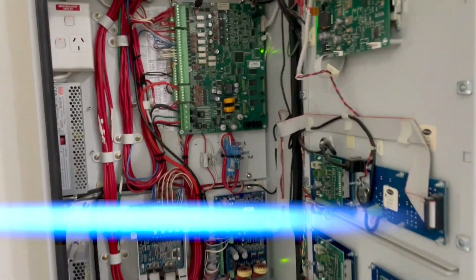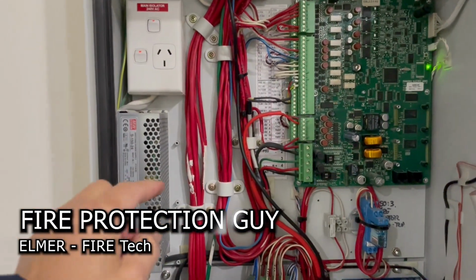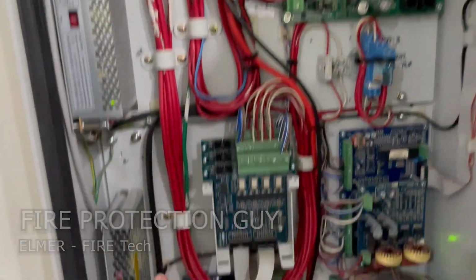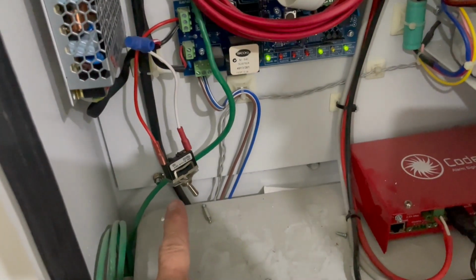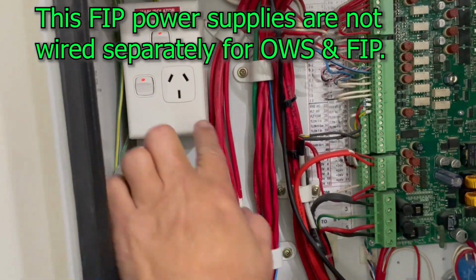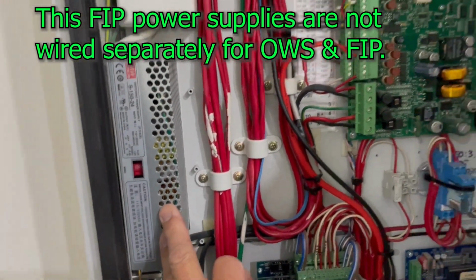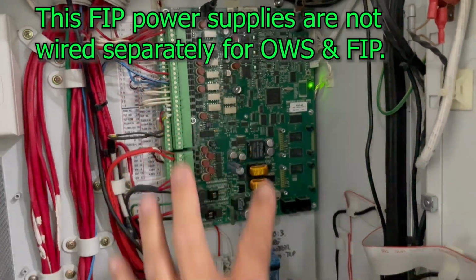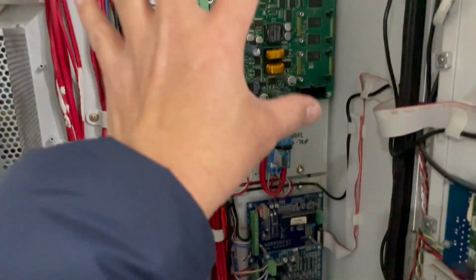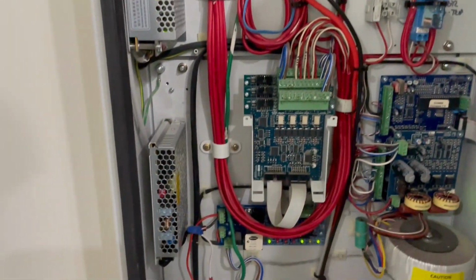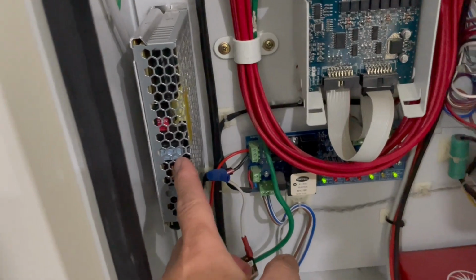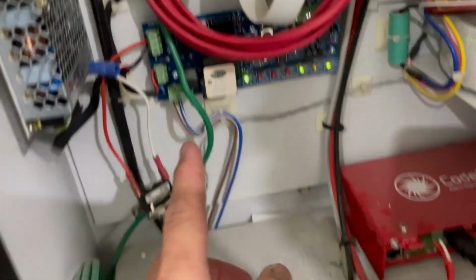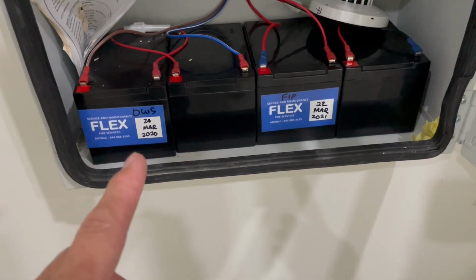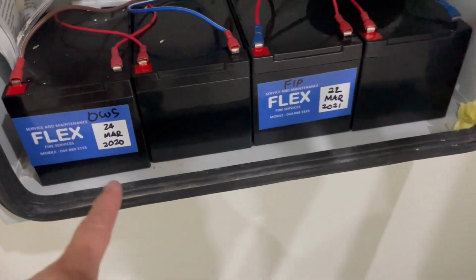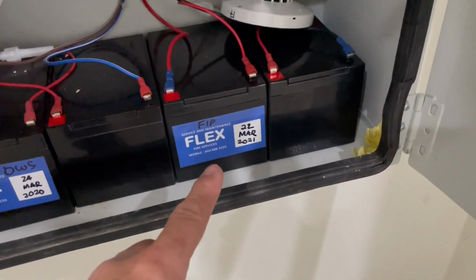While we are here, I'm going to discuss this G3 panel. Why do I have a switch there? It did not exist before. This is because 240 volts power goes to this power supply, which supplies the main board and the other ancillary equipment of the fire detection system, and another power supply for the occupant warning system. That's why they have two separate batteries: a battery for the occupant warning and a battery for the fire indicating panel.